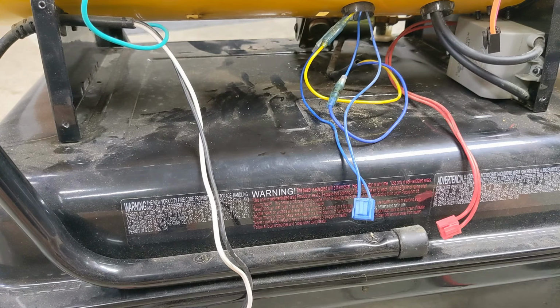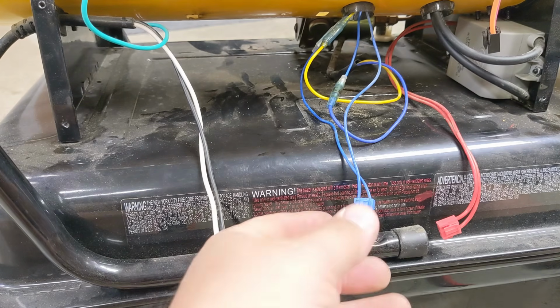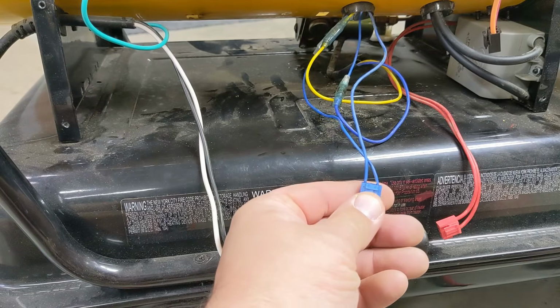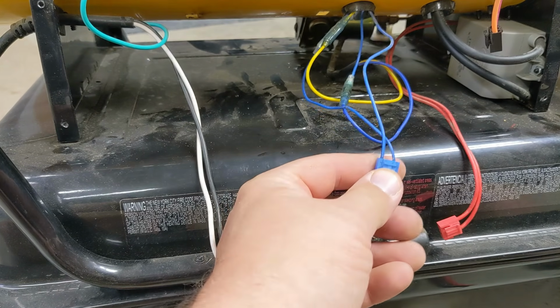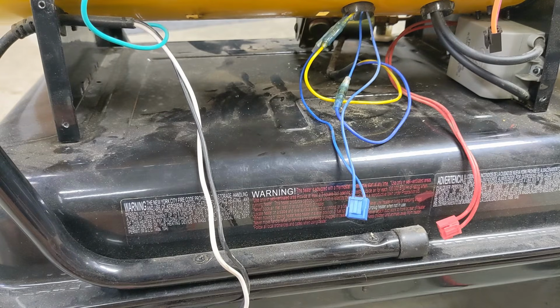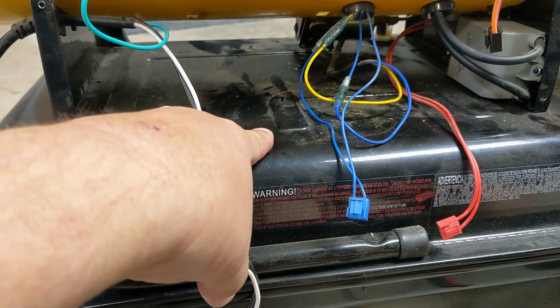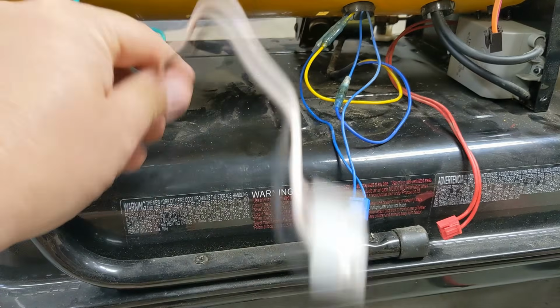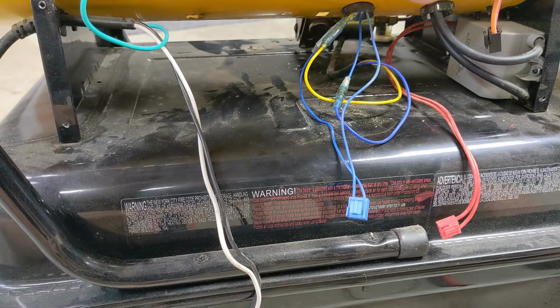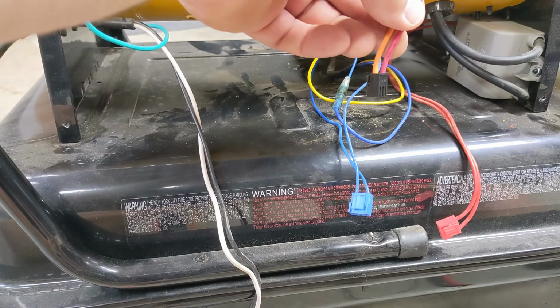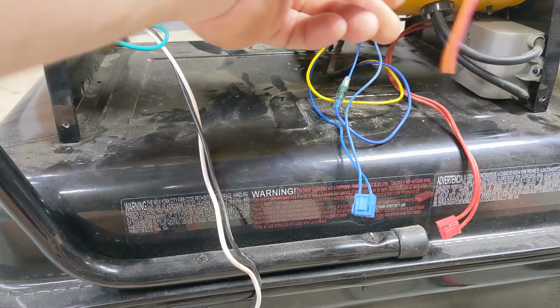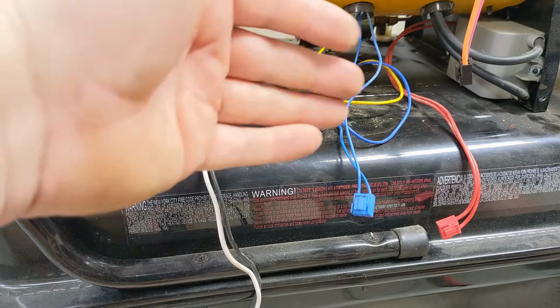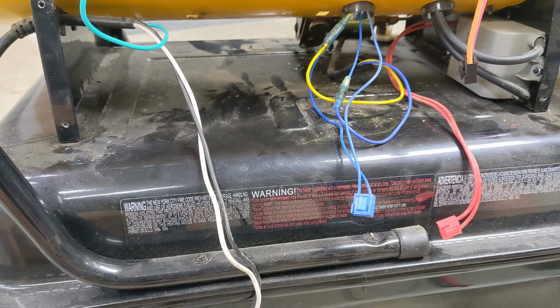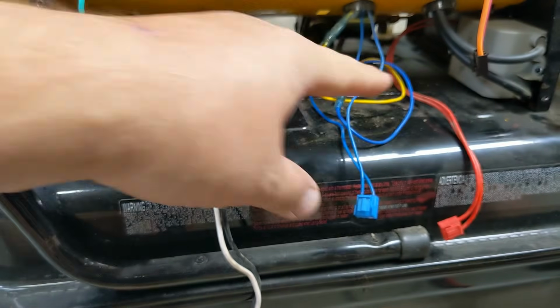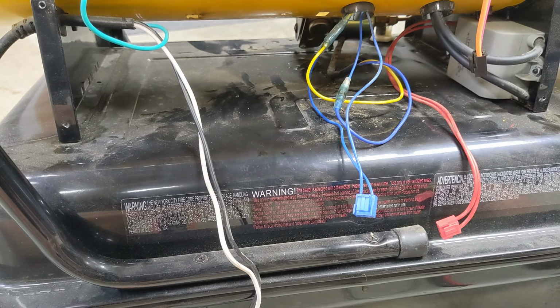Oh, that's nice. Didn't have the camera going. Anyways, what am I thinking? So the board acted as a switch to turn on the fuel pump, right? AC comes in, it went through the board. One of the relays in there sent power to the fan motor that also connected the yellow and blue wire to AC inside the motor unit. The blue wire of that AC goes through the thermal sensor and comes back to this plug.